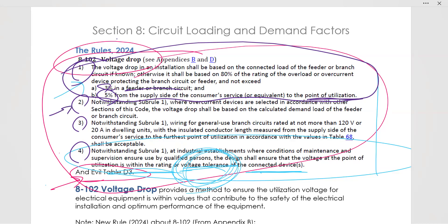Subrule 2 said that if you are in a different section of the code, then you can select the overcurrent devices according to that section of the code. Section 3 said that if you're in a residential circuit, 120 volts, 20 amps, then you can use table 68 to simplify things. And section 4 says if you're in an industrial establishment where there is maintenance and supervision, then the design will ensure that the voltage at the point of utilization is within rating and voltage tolerance of the connected device.